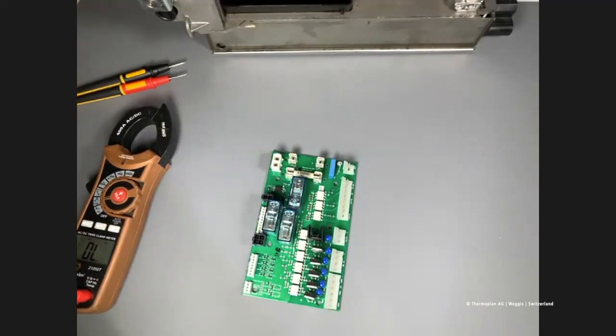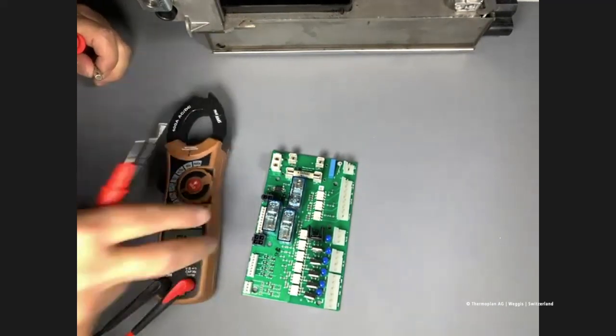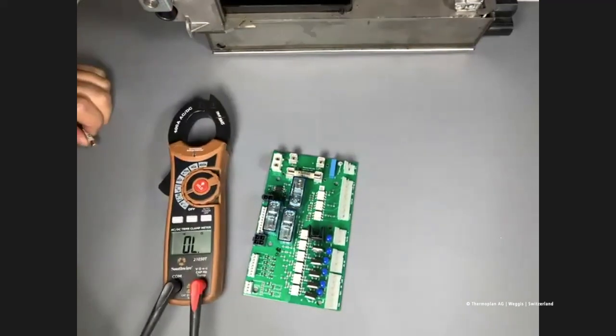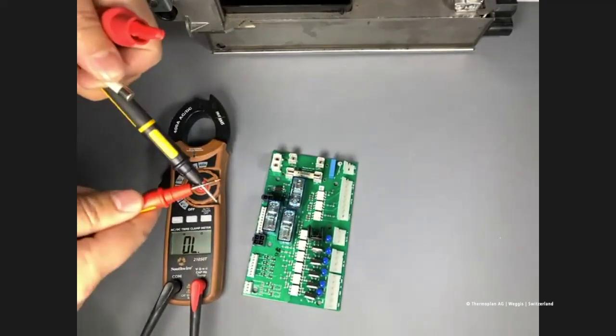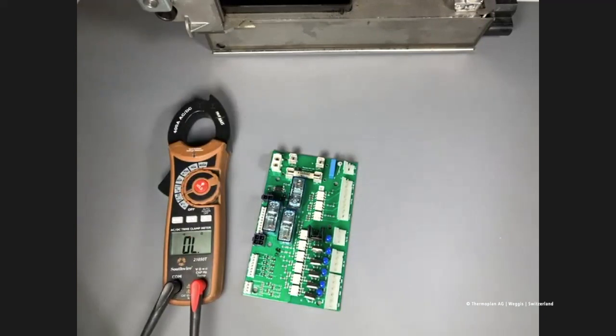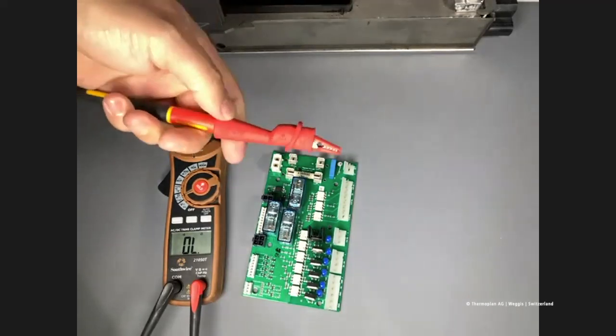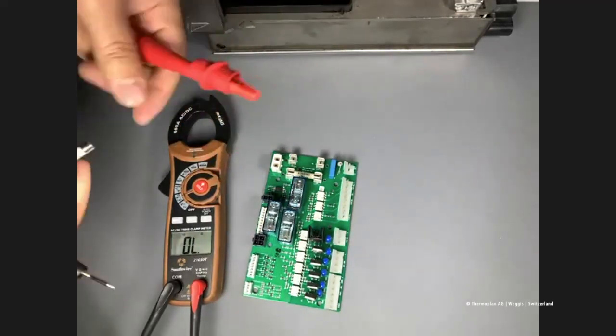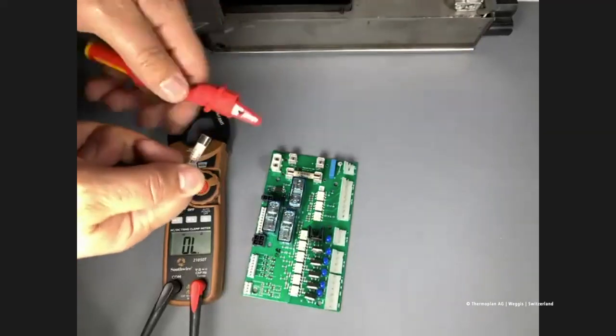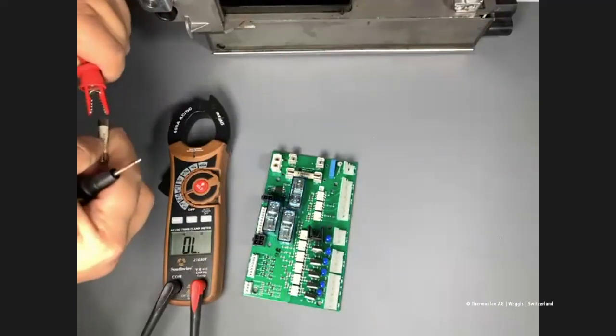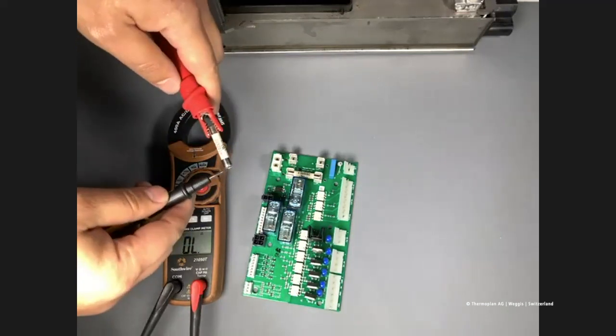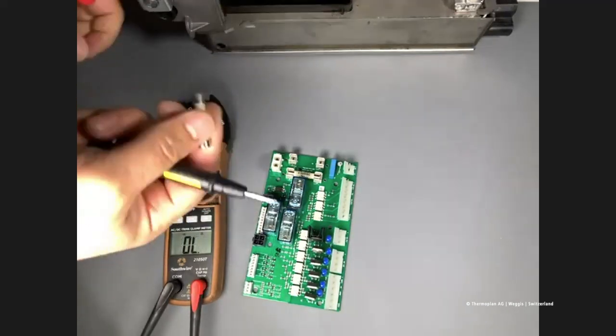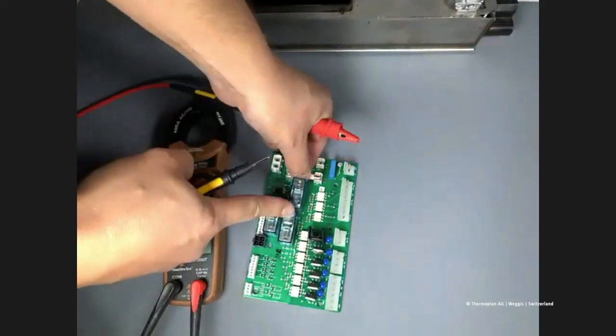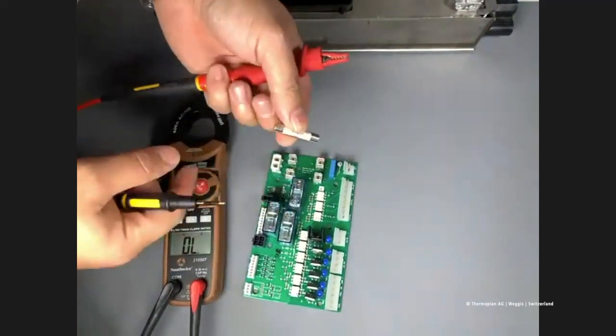So we would simply test the fuses. I'm sure everybody here knows how to test fuses, but I'll walk through it anyway: set our meter to continuity, make sure we have tone. I typically put an alligator clip on here just to make sure I don't get a false reading from touching my meter like this. I'll just hold one end, test it. If it tests bad, then we need to replace it, and we'd go through the same process on the second fuse as well.